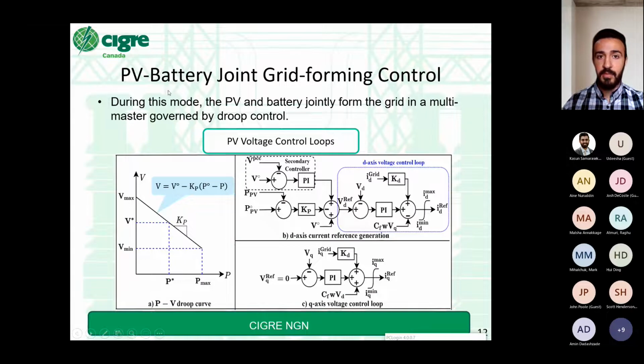I'm going to introduce the PV battery joint grid forming control. In such a case, the PV operates in a grid supporting mode. That's going to form the grid along with the battery energy storage system in a multi-master configuration governed by a droop control. And since this is a low voltage microgrid, P-V and Q-omega droop curves are going to be applied.